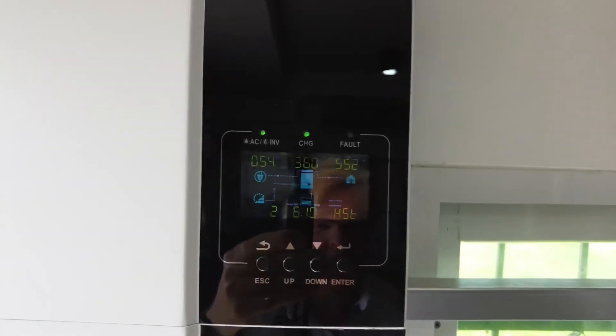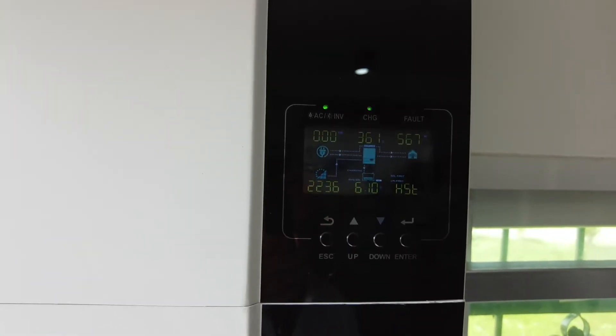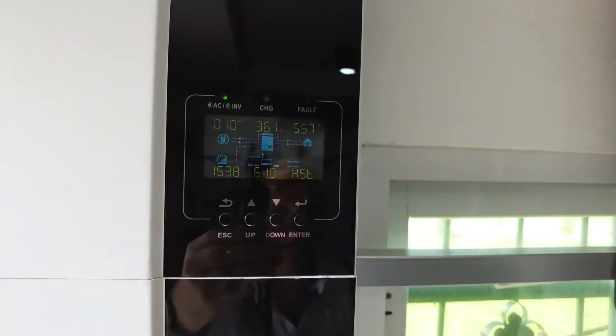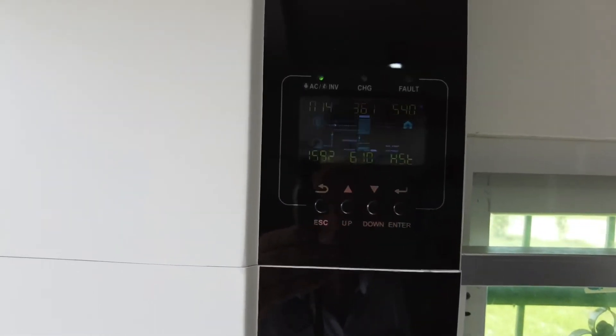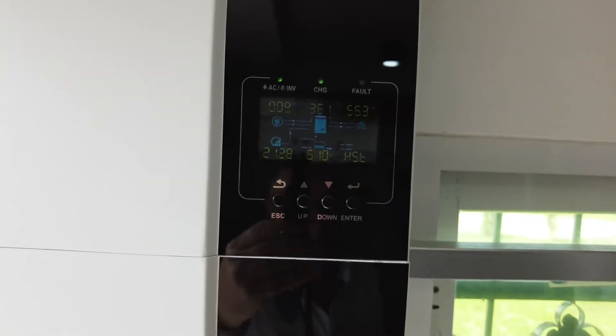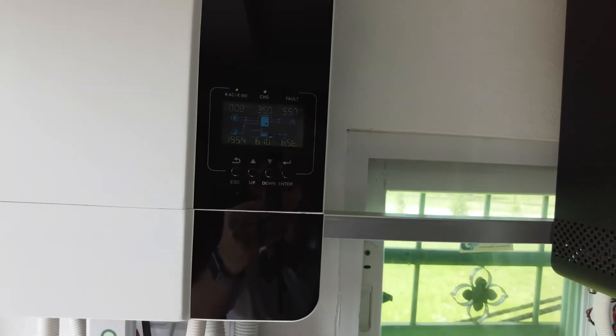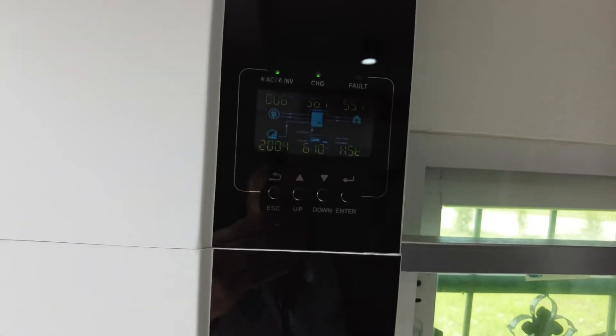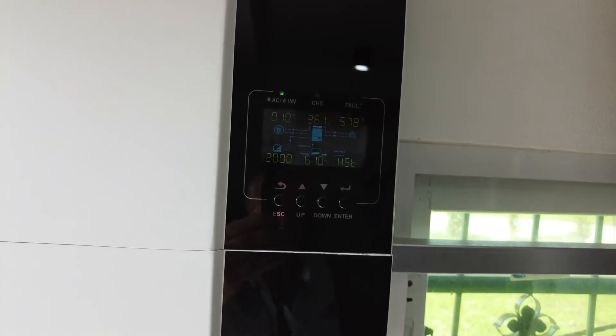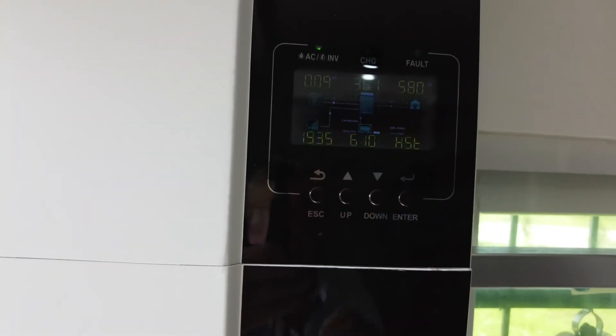Now we are drawing power from the grid. But remember, I just switched the grid off. The reason for that is that I wanted to show that you can have two sources of AC power coming into an inverter. In my case, this is the grid power, but the default setup is my original solar system. So if you had vehicle to load, you could have an automatic transfer switch like I've got, and you could have grid coming in, or you could have power from vehicle to load via the automatic transfer switch.